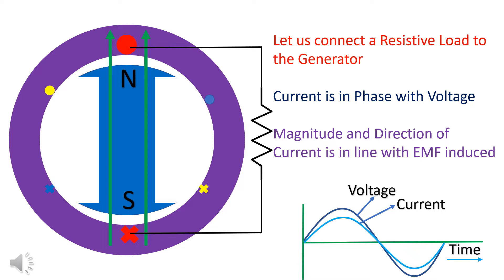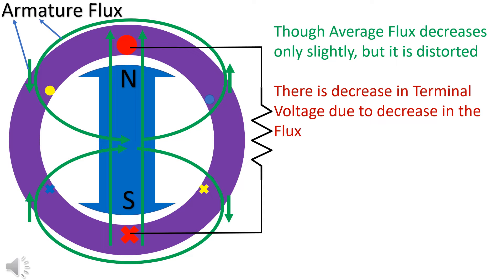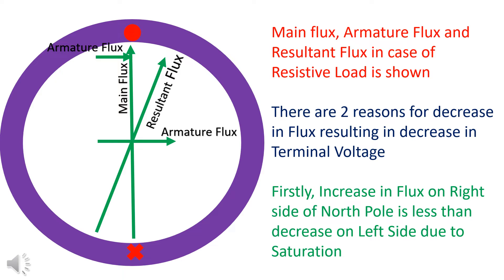Let us see what happens when the resistive load is connected to the generator. Voltage and current are in phase. Direction of current is same as that of the EMF. Applying right-hand thumb rule, armature flux is as shown. Flux increases on one side and decreases on the other side of the conductor. Though there is not much change in the average flux, it is distorted.